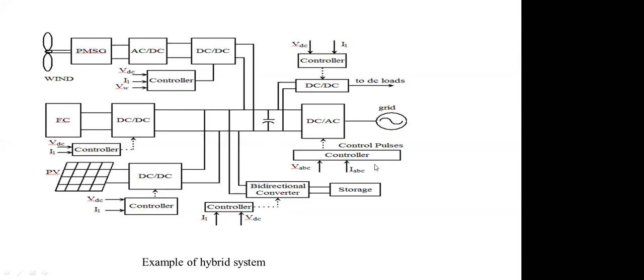Even the way to connect storage involves a lot of work - do you want to connect it at the DC link or the AC link, or have a combination of storage types, like battery and ultra capacitor, or compressed air, or flywheel. Depending on the storage type, the converter will vary, and every converter has to be locally controlled and monitored at the central level also.